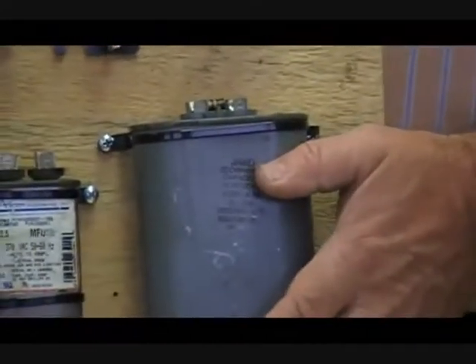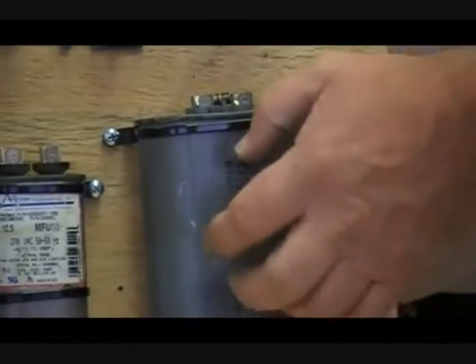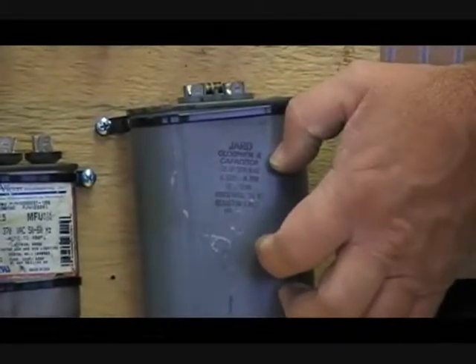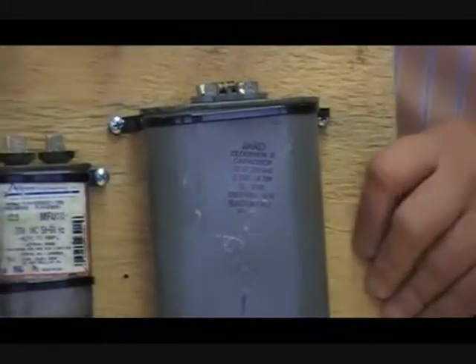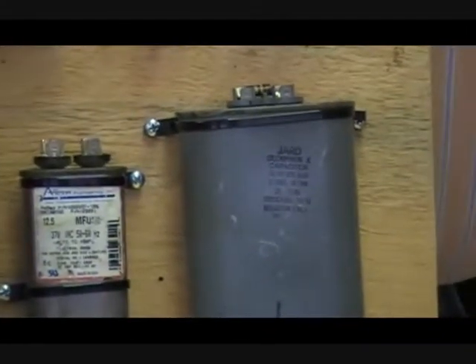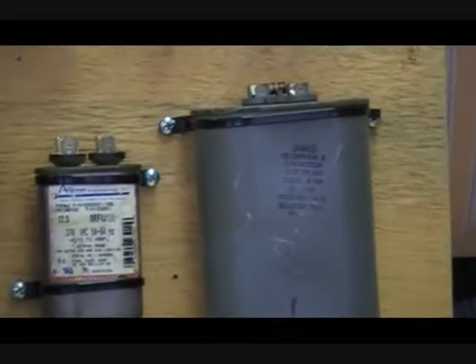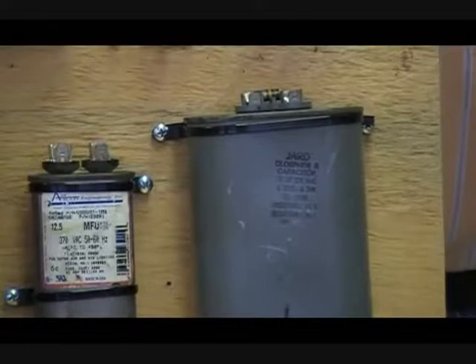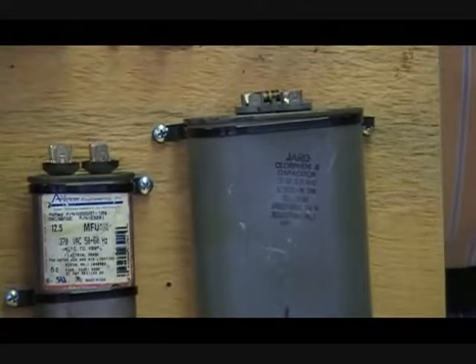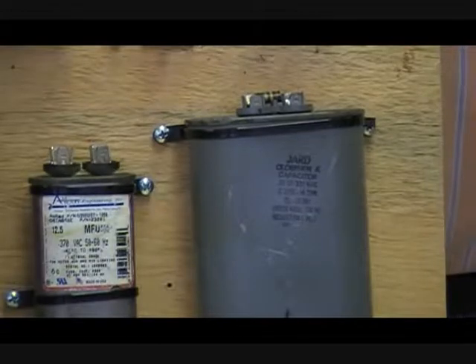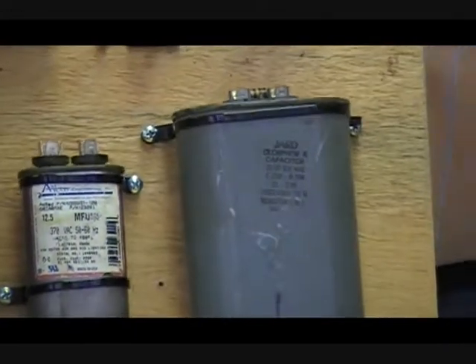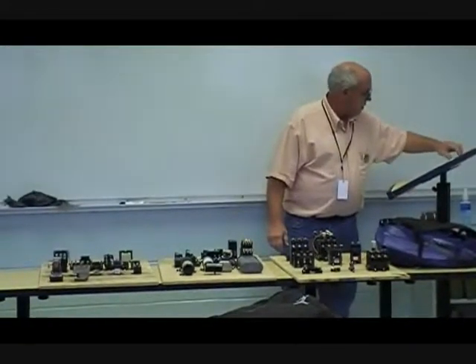The ratings are going to be in microfarads and the maximum voltage. Like I say, we'll go a little deeper into that, but I can tell you this right now. Don't ever exceed the maximum voltage. Does the size really matter? The size of the capacitor in microfarad, yes, it does. It has to match the motor. That's part of the run and starting components of a motor.